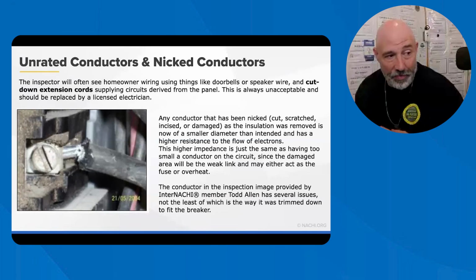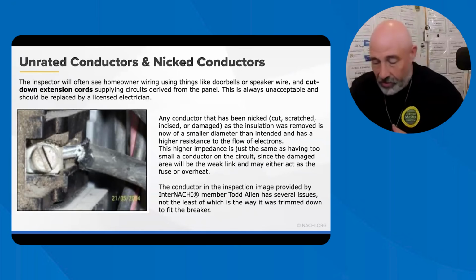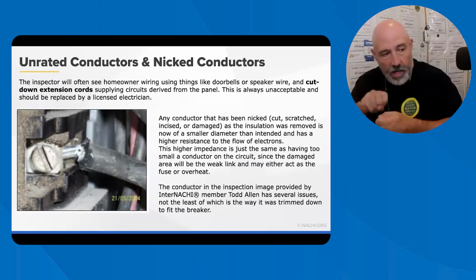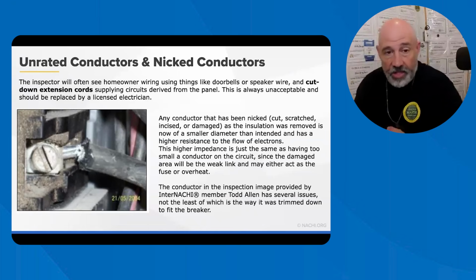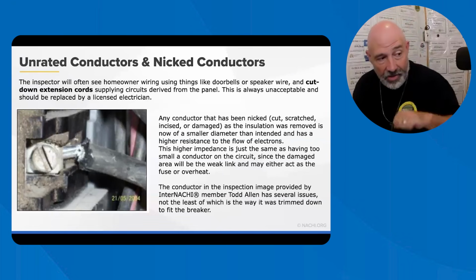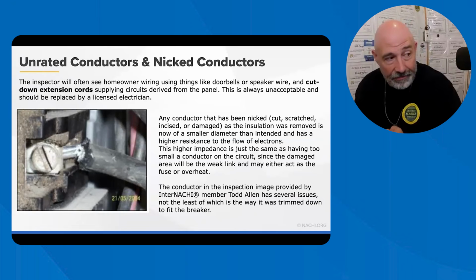So here's another picture where the conductor is definitely oxidized, but it also looks like they trimmed too much of the insulation off the electrical wire. So think about it: you're putting all this pressure on and then it releases, and you're putting all this pressure on and it releases, and it does that over time. It's going to start melting the rubber sheathing that it's on. So make sure all those lugs are properly seated.